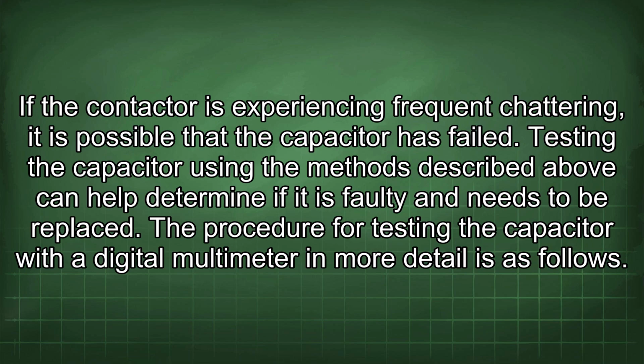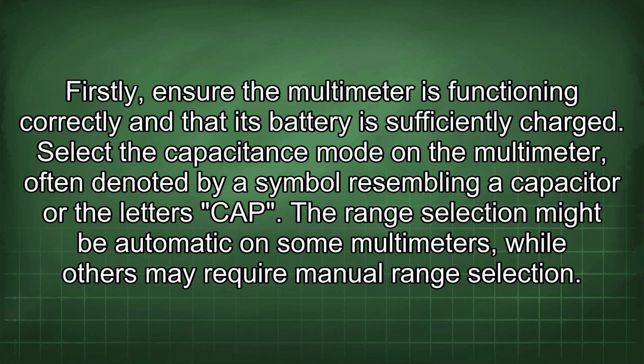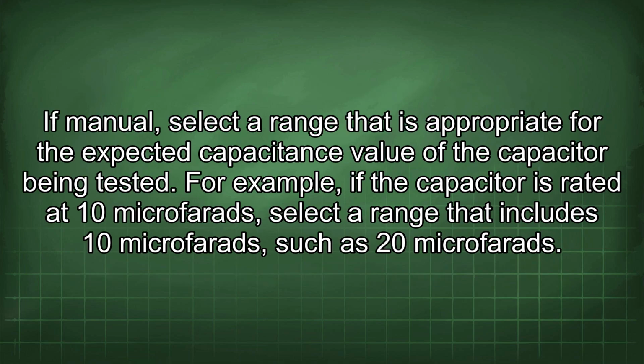The procedure for testing the capacitor with a digital multimeter in more detail is as follows. Firstly, ensure the multimeter is functioning correctly and that its battery is sufficiently charged. Select the capacitance mode on the multimeter, often denoted by a symbol resembling a capacitor or the letters CAP. The range selection might be automatic on some multimeters, while others may require manual range selection. If manual, select a range that is appropriate for the expected capacitance value of the capacitor being tested. For example, if the capacitor is rated at 10 microfarads, select a range that includes 10 microfarads, such as 20 microfarads.